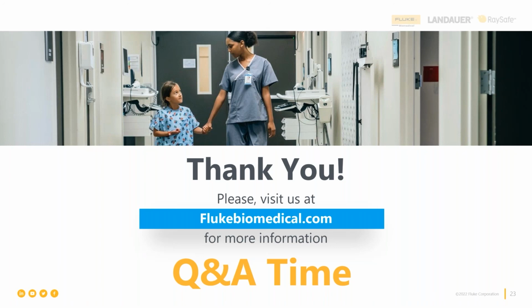Okay. How do you conduct electrical safety testing using a multimeter? And they gave the example using the Fluke 289. Okay, so not advised. The Fluke 289 is an industrial multimeter, and therefore you would have to improvise the appropriate test load. And that is prescribed in the International Electrical Safety Standards, and you shouldn't try and invent that or improvise that yourself. Use a safety analyzer.